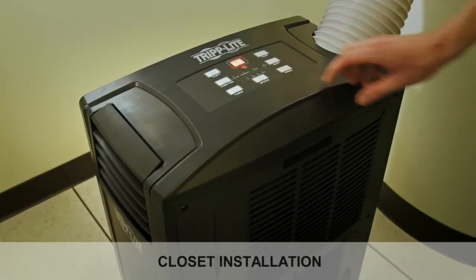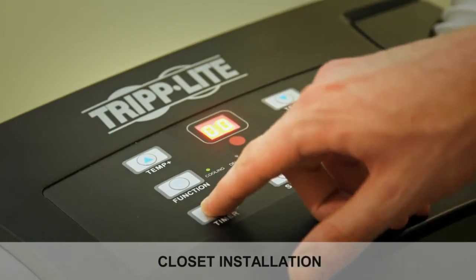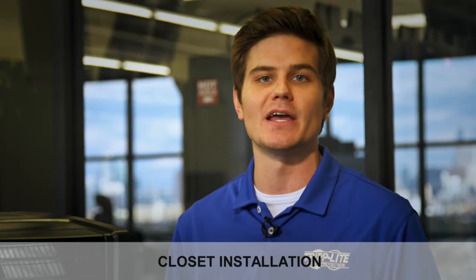If the unit will operate in a confined space such as a closet, you must supply makeup air in order to maintain efficient airflow. A vent of at least 100 square inches installed near the bottom of the door should supply adequate makeup air for a typical closet. Consult applicable building codes for more information.